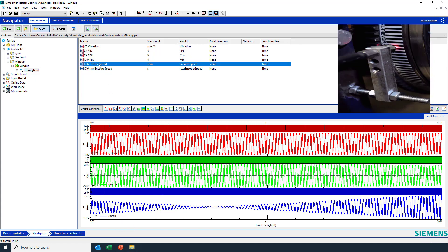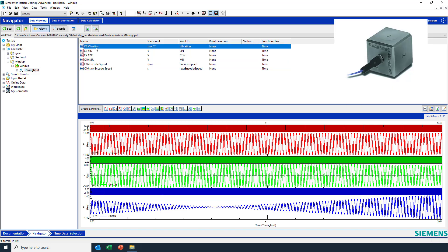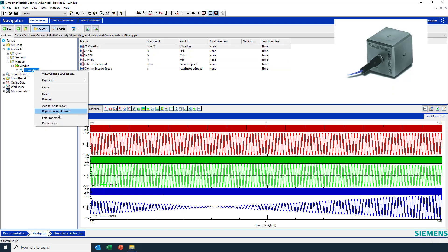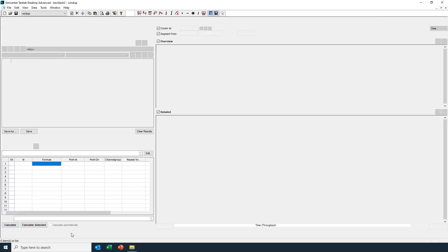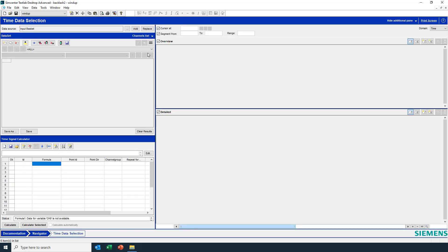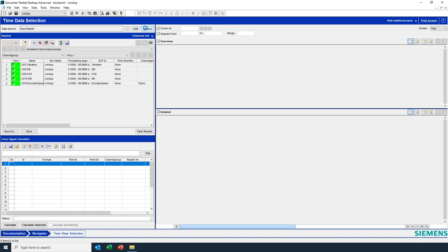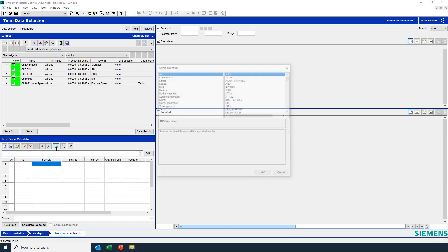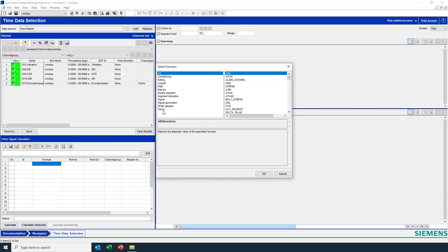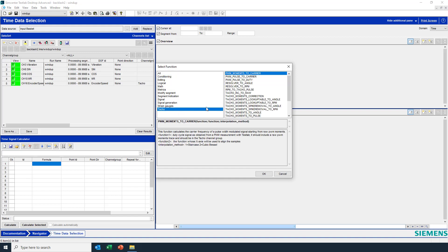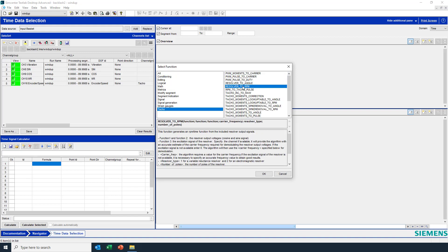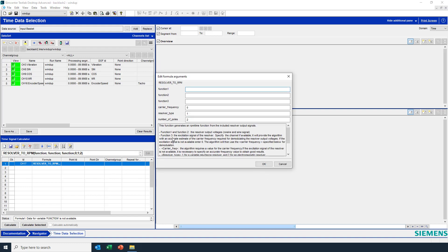We also have an encoder which we'll look at here in a second, and we have the vibration data. I'm going to put this data in the input basket to do some analysis. Hit replace here, and the first thing I'm going to do is calculate the rotational speed of the resolver. So I'll pick resolver to rpm here.